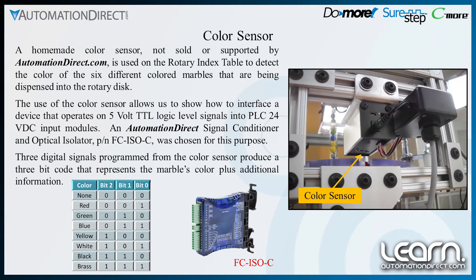Using the color sensor gives us the opportunity to show how to take a device that operates on 5V DC TTL logic level signals and interface it to PLC 24V DC input modules. We chose an AutomationDirect signal conditioner and optical isolator, part number FC-ISO-C, for this task. Three digital signals programmed from the color sensor produce a 3-bit code that represents the marble's color plus some additional information. See the truth table shown here.